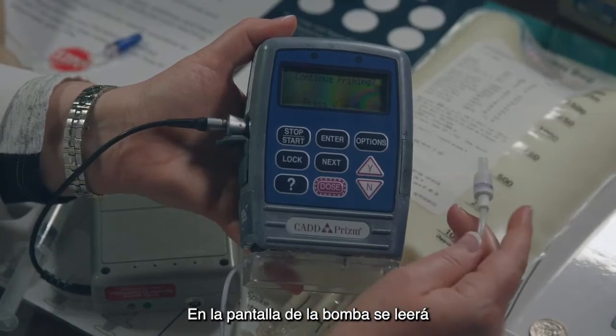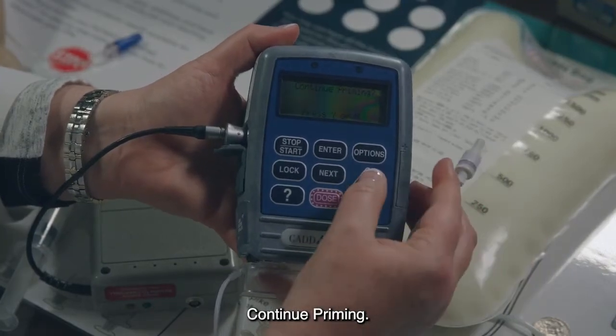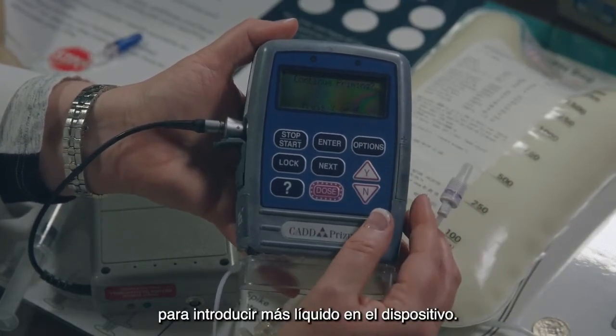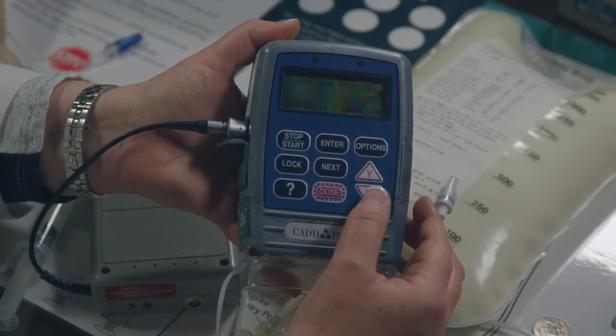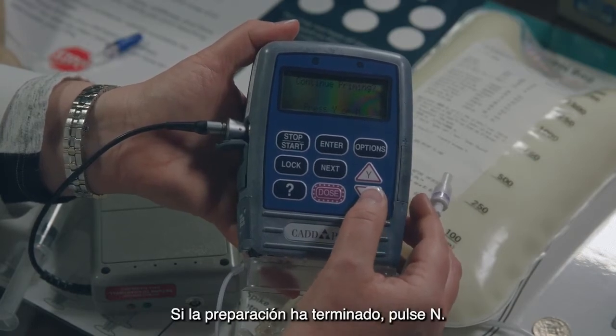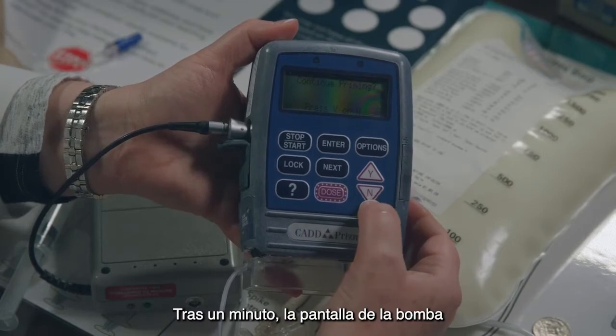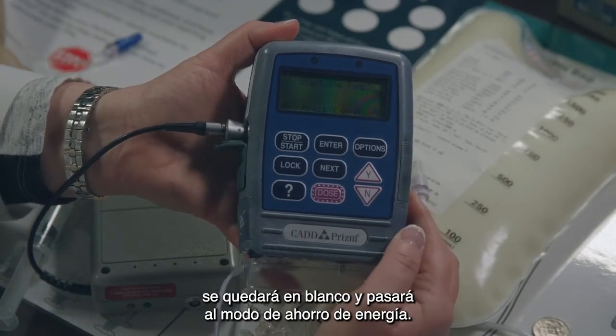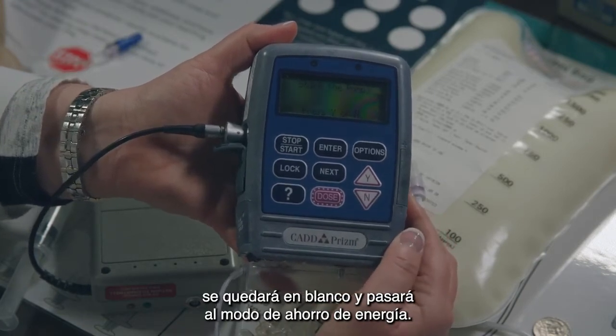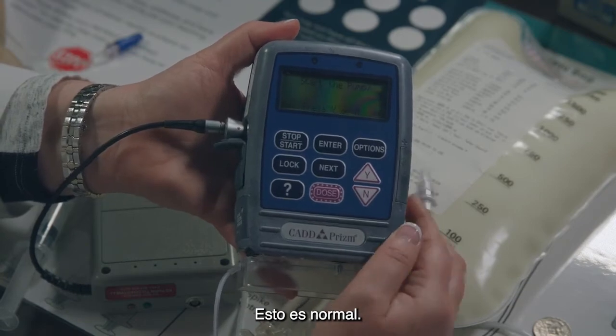Pump display will read Continue Priming. Press and hold the Y button to prime more fluid into the tubing. If priming is complete, press N. After a minute, the pump screen will go blank, going into power save mode. This is normal.